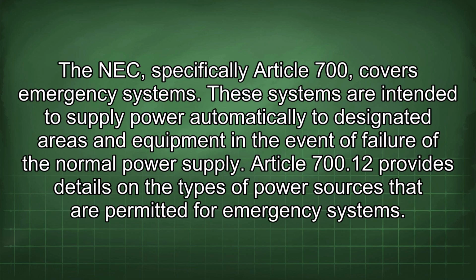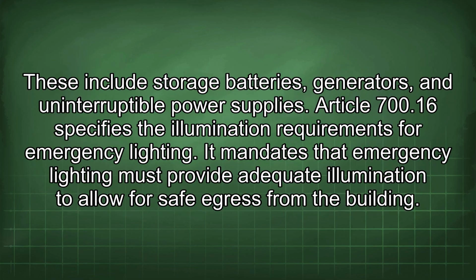The NEC, specifically Article 700, covers emergency systems. These systems are intended to supply power automatically to designated areas and equipment in the event of failure of the normal power supply. Article 700.12 provides details on the types of power sources that are permitted for emergency systems. These include storage batteries, generators, and uninterruptible power supplies.